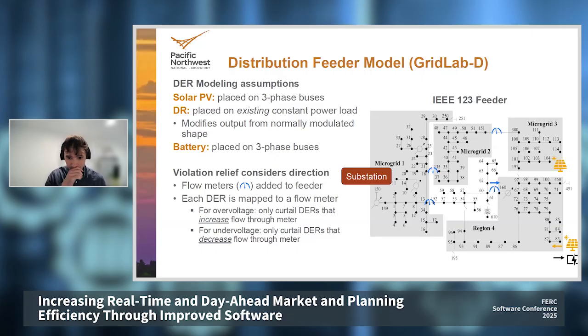We're also trying to simulate a more realistic system in which the distribution system operator doesn't have all the information on every single DER and load, but might have flow meters at specific points. We set up a framework to simulate a distribution system operator monitoring those flows, and if there's under or over voltage in the system, it can curtail DERs in the appropriate section to respond.